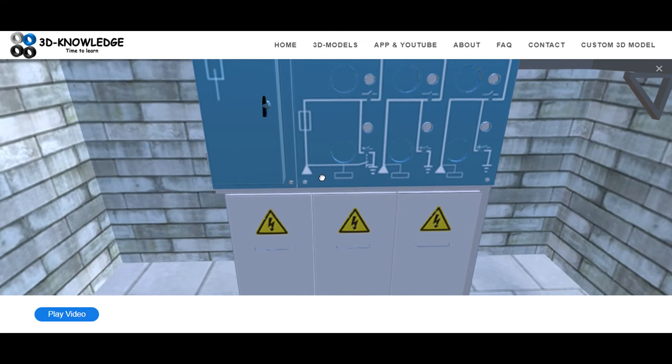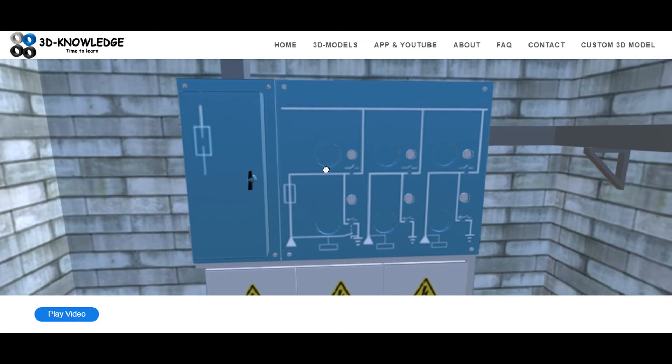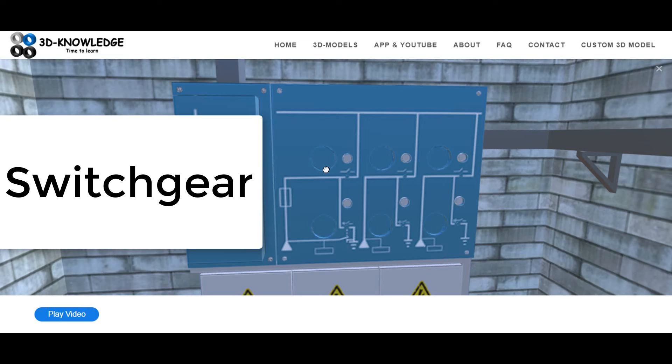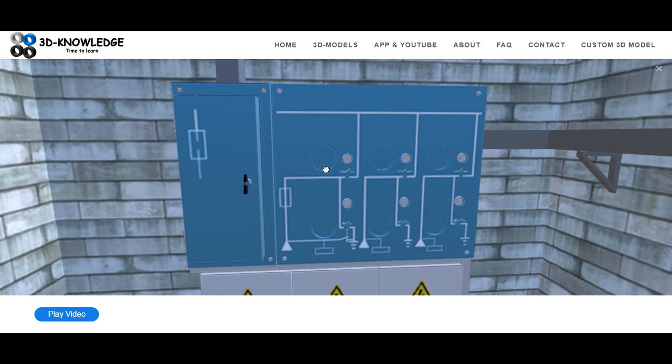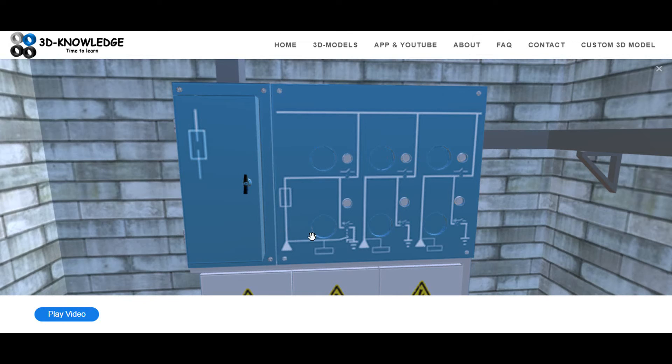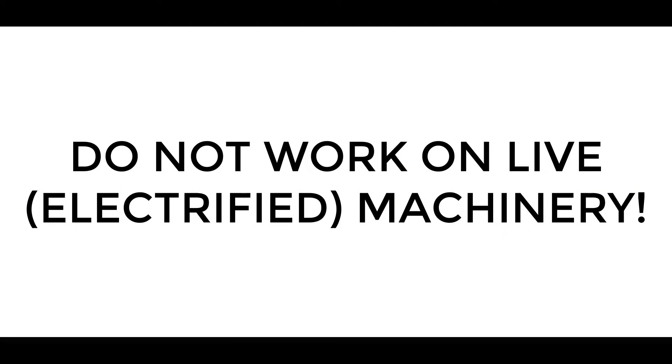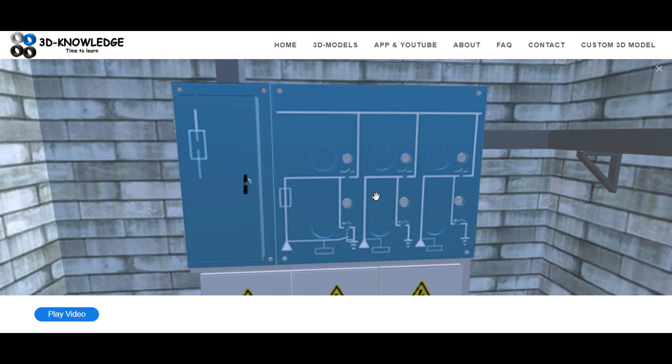Switchgear is used to protect the generator. It prevents any damage that may occur due to overvoltage or overcurrent. So if there's any large fluctuations in voltage in the line or current, the switchgear will open kind of like a large switch but it's done automatically and this protects your generator. Remember the generator is quite expensive, you don't want huge currents and huge voltages going to the generator. In addition to that, it's also very useful if you're doing maintenance on the generator to isolate it. In fact it's not just useful, it's a requirement. You'll need to isolate the generator completely so it's safe to work on and you will isolate it here at the switchgear.